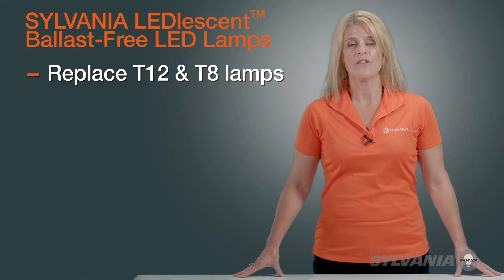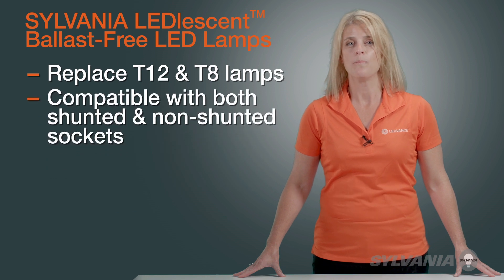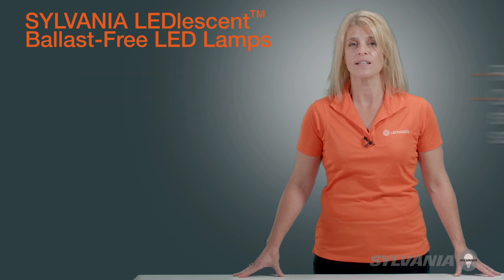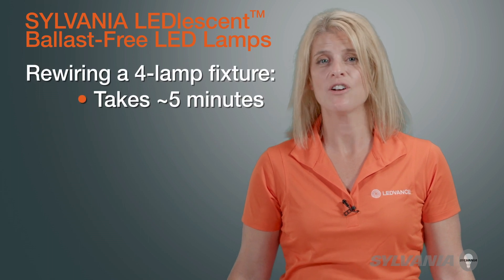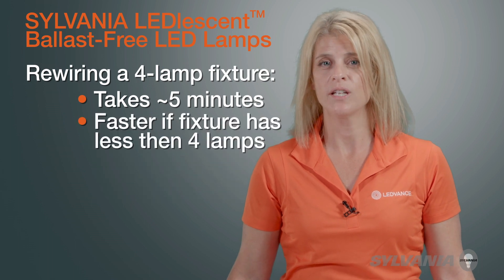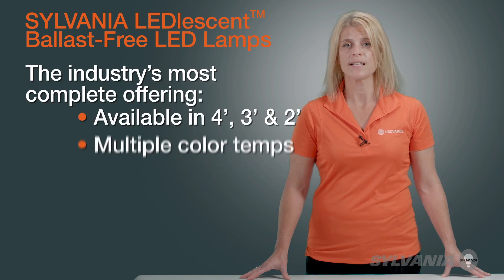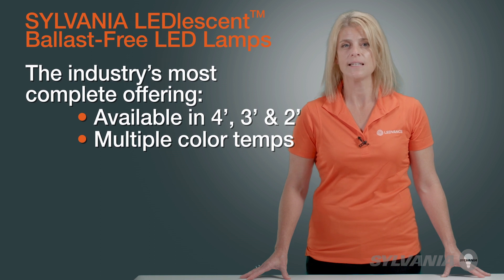Sylvania LEDlescent lamps replace T12 and T8 bi-pin fluorescent lamps. They are compatible with both shunted and non-shunted sockets, so there is no need to replace these parts unless the existing sockets have deteriorated. Rewiring an existing four-lamp fluorescent fixture can be accomplished in place in about five minutes. If the fixture has less than four lamps, the retrofit is even faster. Available in four, three, and two-foot lengths along with multiple color temperatures, Sylvania LEDlescent Ballast-Free LED lamps are the industry's most complete offering.